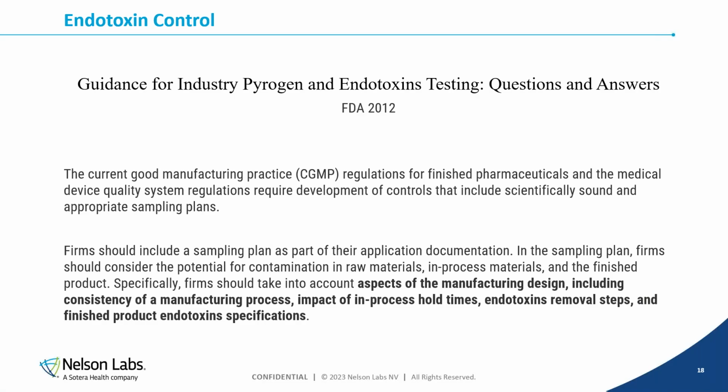I wanted to start with a statement published by the FDA in Questions and Answers in 2012, and this is actually telling you what to do. If you produce pharmaceuticals, but the same principles are applicable for medical devices, you should look into every aspect of the manufacturing design: the impact of process holding time, endotoxin removal steps, etc. So it's not only end product testing.